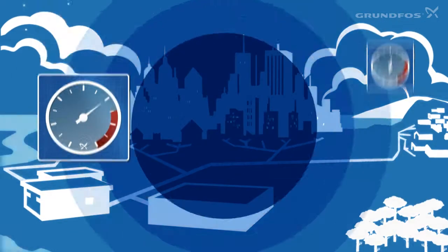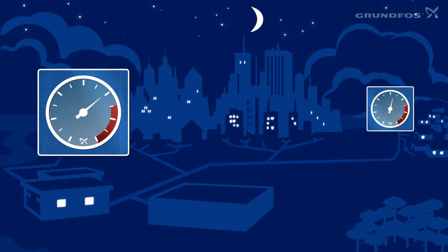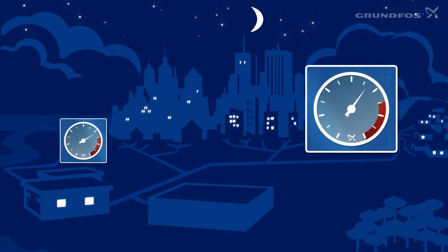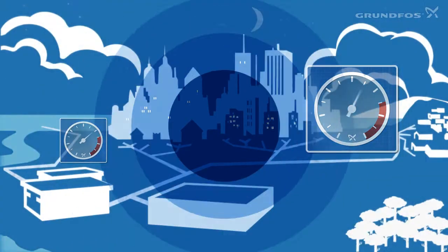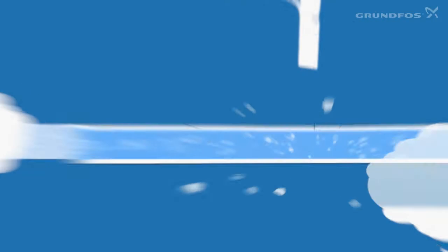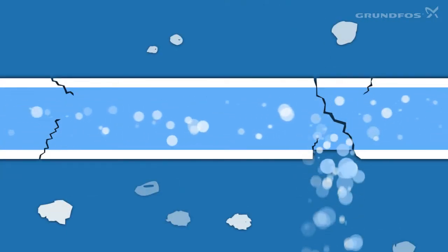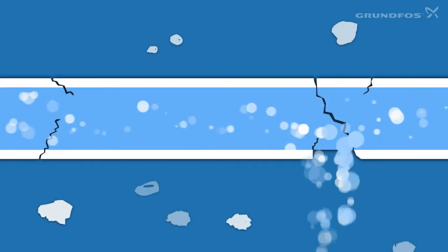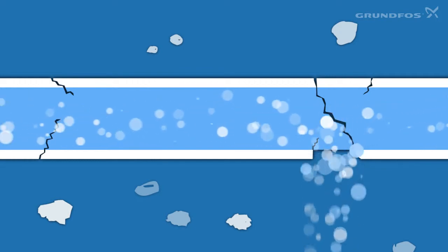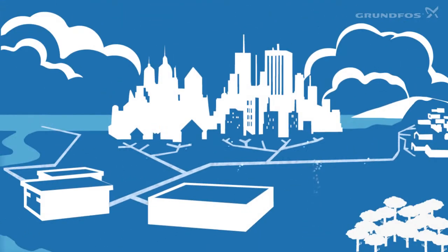When the pressure remains constant at the pump but the flow changes to meet the varying demand, pressure changes at the critical point. These fluctuations in pressure throughout the system increase stress on the pipes, cause water leakage to rise when there is little demand for the water, and waste energy.